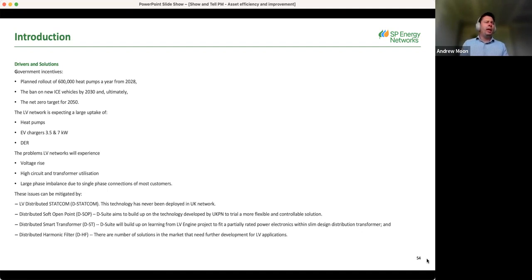In the UK, we typically have single phase connections to properties, and these are thought to be reasonably well distributed across the phases, but there is masking of exactly which customers connect to what phase, and whether there's any phase imbalance, which will drive issues later on. These issues will become apparent when we increase penetration levels of heat pumps, EV chargers, which at domestic level would be 3.5 to 7 kilowatts, and things like photovoltaic panels. I doubt we'll see wind, but it's mainly photovoltaics. When we increase penetration levels of PV, we see voltage rise issues and difficulty maintaining within statutory limits towards the end of the feeders, especially on radial circuits.